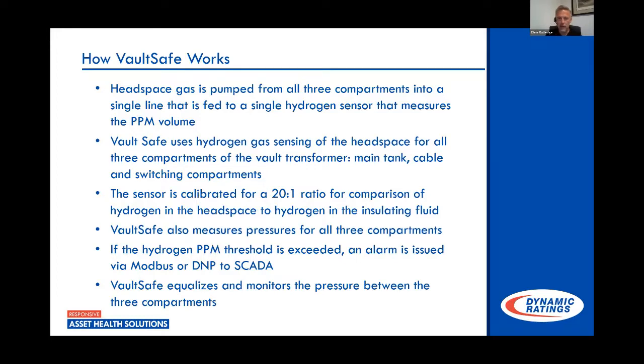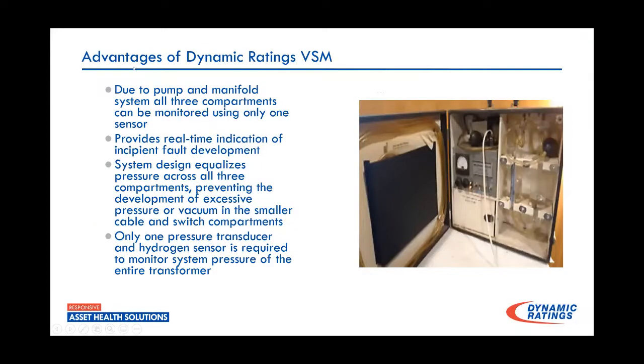And we do provide an output that lets you know what that pressure's at. Again, alarms are set for low values of pressure, because we do want to catch a leak, and that could be an oil or a gas leak is going to result in that low pressure. But we also don't want something out there with 10 psi on it either. I mean, that's also problematic. So that allows us to watch that across all three compartments with the monitor. And we've talked about this, and this was the old TCG tester. And again, this was kind of the birth of this idea, came from running this test.